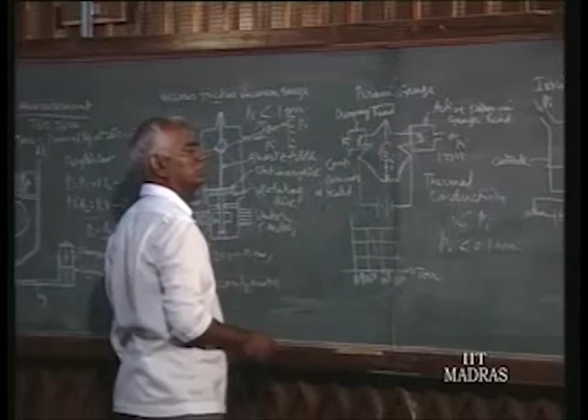We have learnt that resistance is proportional to temperature under resistance thermometers. So the resistance is low. Now you adjust the potentiometer so that the imbalance current is 0. So at 1 torr, you will have a 0 reading here. Now send a known vacuum. You can apply a known vacuum because it's a calibration process. When we apply a vacuum less than 1 torr, the temperature will increase because fewer molecules are taking the heat from the filament. The imbalance will come, and you will have some current value here. So that is for one pressure. Similarly, you can use it for different vacuum pressures. 10 to the power minus 1 to 10 to the power minus 3 torr is the normal range for the Pirani gauge.